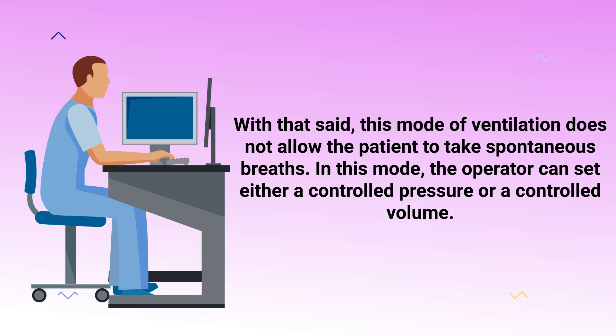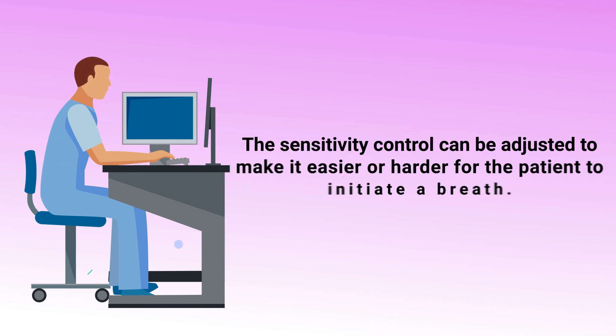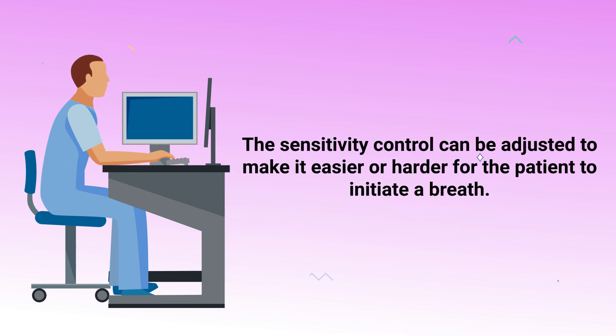In this mode, the operator can set either a controlled pressure or a controlled volume. The sensitivity control can also be adjusted to make it easier or harder for the patient to initiate a breath.